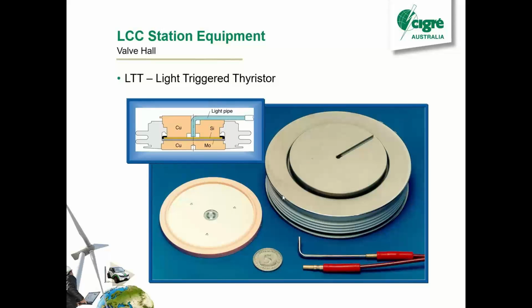So you used to have the electrically triggered, where you had a metallic gate that you'd put a voltage into, but now we can go to these light-triggered ones, which does remove some material off the valve and theoretically makes it a bit more reliable. And we've got light-triggered on our latest pole, but we're still using electrically triggered on our older pole. You can see the fiber optics go straight into the middle of the thyristor there.